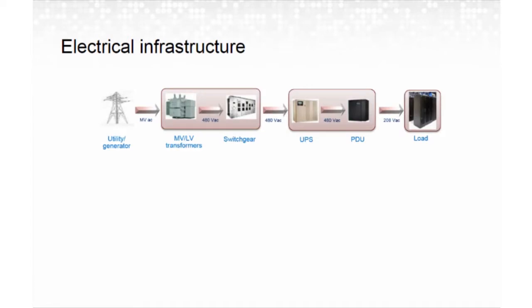Next, I want to look at a typical electrical infrastructure. So you have utility coming in at a higher voltage, goes through some kind of transformation to bring it down to a voltage to be utilized by the facility, maybe 480, goes through some switchgear. If it's a critical facility, there might be a UPS, and then some kind of transformation to get it down to the utilization voltage out at the equipment.